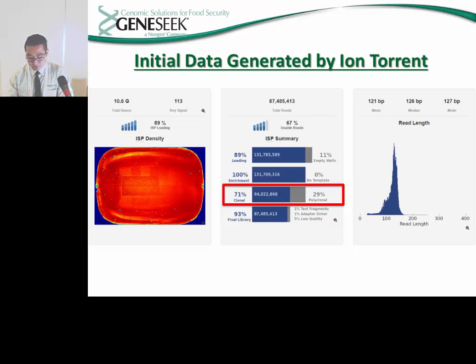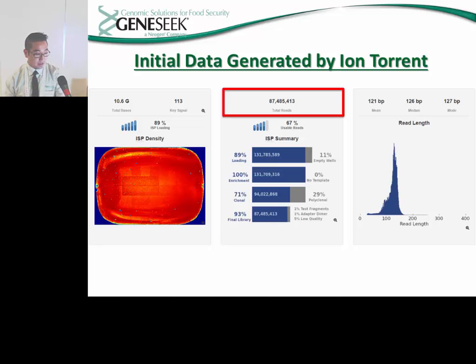Lower loading percentages indicate problems with amplification and can be used to determine whether certain parts of the process need modification. We are also interested in the ratio of clonal to polyclonal samples. A successful run will always have a higher number of clonal samples than polyclonal; GeneSeek has found the clonal to polyclonal ratio needs to be around 7 to 3. If the polyclonal samples greatly outnumber clonal samples, this suggests an incorrect amount of pooled DNA was loaded into the Ion Chef for template preparation. The final piece of initial data is the total number of reads generated per run. With our modified process, we are currently generating on average 80 million reads per run, meaning each sample is generating around 400,000 reads.